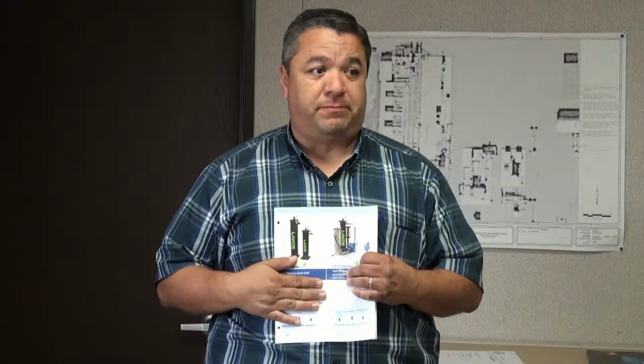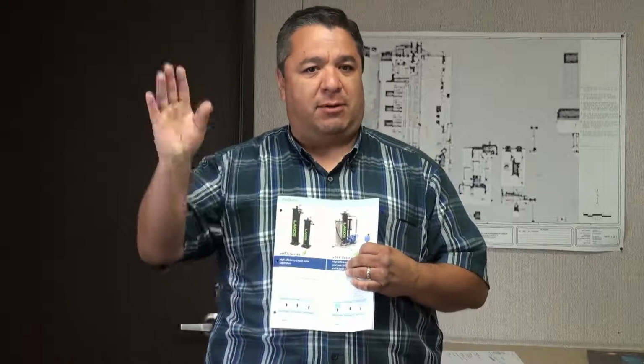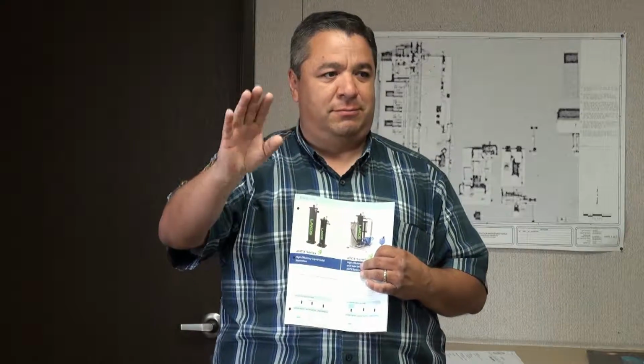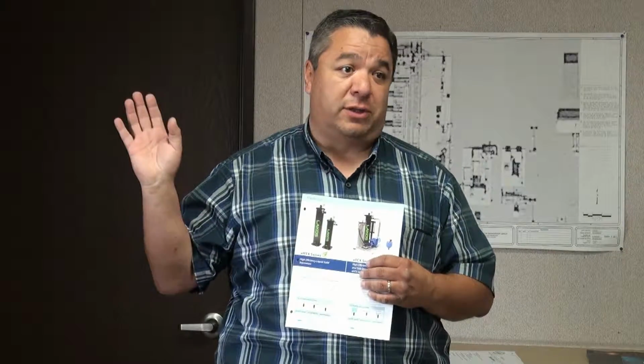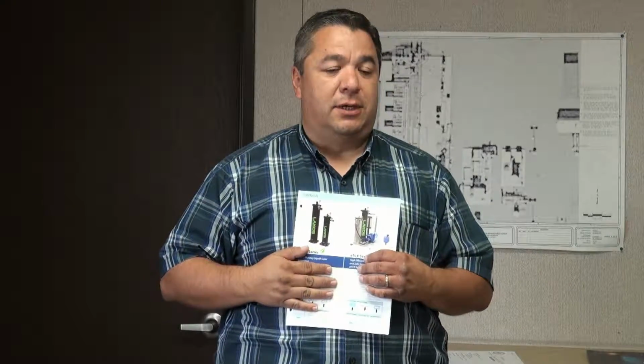As long as the tower's on, the separator should be on. Now, a lot of people leave the separator running 24/7. It's an energy thing, some people don't care too much about it, some just make sure the tower's clean. Towers are great air scrubbers, they scrub air and throw that crap in your basin, which will protect your chiller and your pumps. That's why they let them run. But a lot of people automate it: tower's on, Lakos is on; tower's off, Lakos is off.